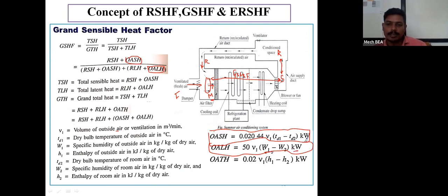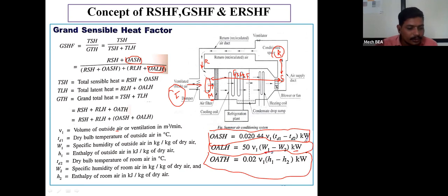Small w1 is the specific humidity of the outside air or fresh air, and small w2 is the specific humidity of the required room condition or recirculated air. The addition of outside air sensible heat plus outside air latent heat gives the outside air total heat, and that outside air total heat will be given by the equation 0.02 v1 (h1 minus h2), in terms of kilowatt.